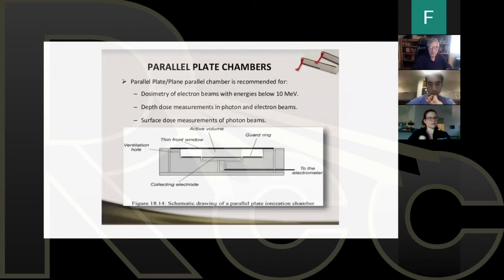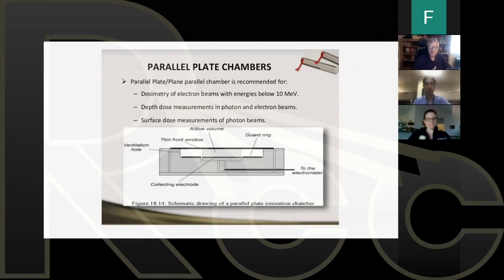This is what a plane parallel chamber looks like. It has a top and it has a bottom. These are the components of a plane parallel chamber. In the TG51 protocol, which I use, it's recommended for electron beams of lower energy. And we can also use it for a variety of other reasons too. But you can see from the cross-sectional diagram that the chamber clearly has a top and a bottom and must be used in the correct position, especially with electrons, because the electron has a depth dose that falls off so quickly that it could make a big difference with the lower energy beams that we saw.